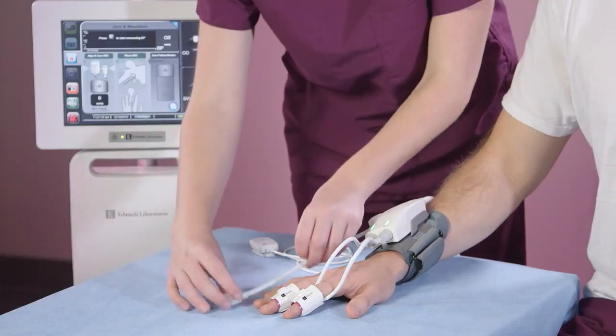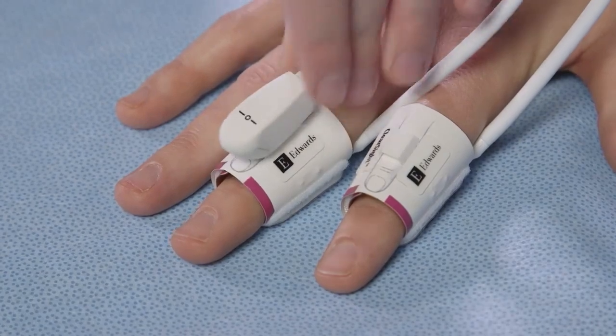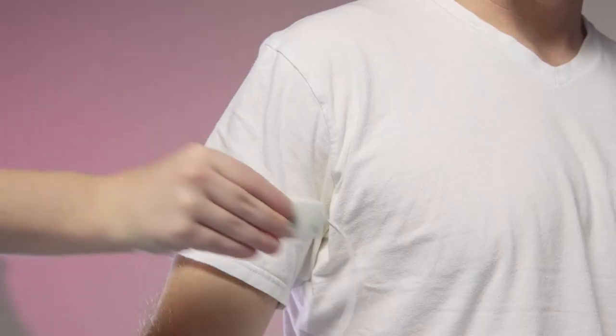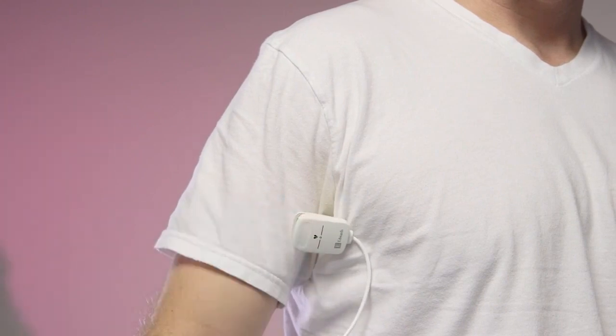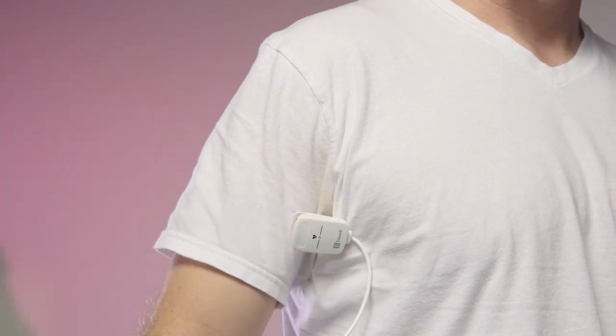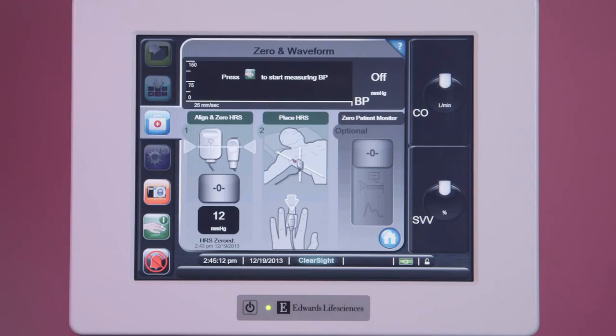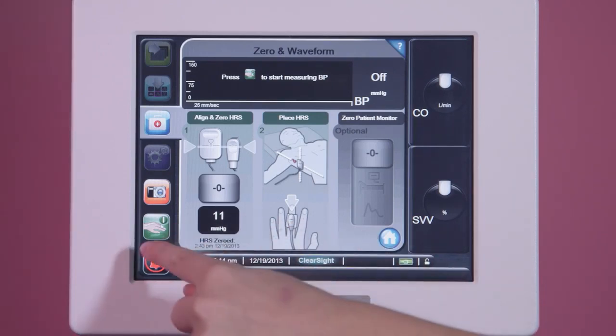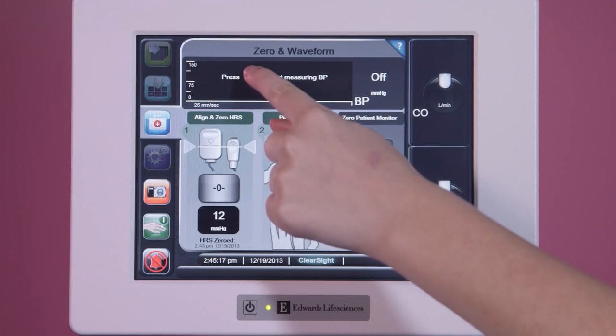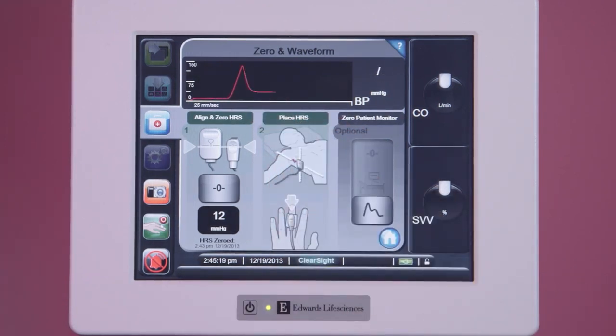Connect the finger component on the tab to the finger cuff. Connect the heart component to the patient at heart level. To do so, the user may either tape it to the patient or use an HRS body pad. To start monitoring, tap the green pump unit Start-Stop icon on either the navigation bar or in the blank arterial waveform display. An arterial waveform will appear at the top of the screen. The system is now measuring continuous, non-invasive blood pressure displayed as a 5-beat average. Other hemodynamic parameters are displayed at a 20-second average.